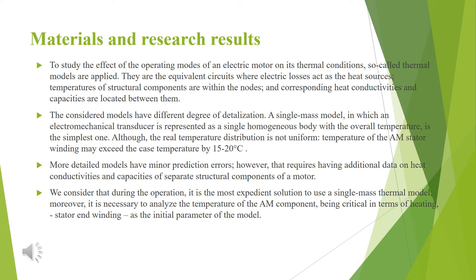Materials and research results. To study the effect of the operation modes of an electric motor on its thermal conditions, so-called thermal models are applied. They are equivalent circuits where electric losses act as heat sources. Temperatures of structural components are represented within the nodes, and corresponding heat conductivities and capacities are located between them.